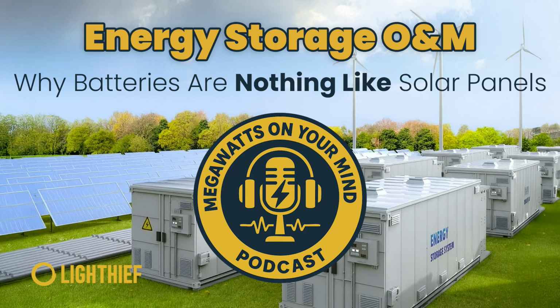Now let's address the crucial question for understanding storage value. How does it serve grid stabilization, and why are grid operators willing to pay for this service? The electricity grid must be balanced every second. Generation must equal consumption plus losses. If generation exceeds consumption, grid frequency rises above nominal 50 Hz. If consumption exceeds generation, frequency drops.